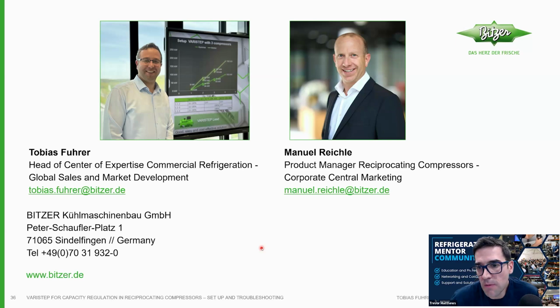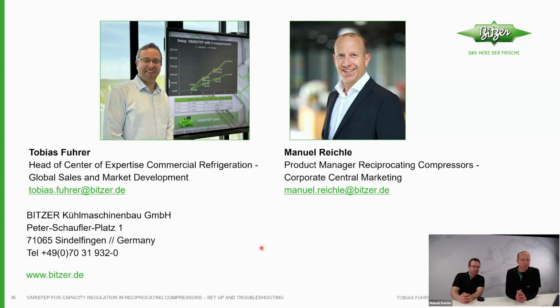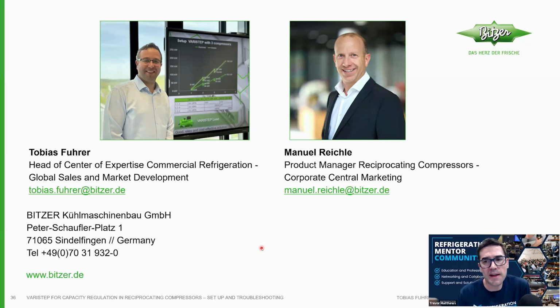Amazing. A couple more here. Thank you so much for your time. The question is, what is the cycle time for the pulse, or is there a cycle time on loading and unloading? It's not a fixed cycle time in the IQ module, but on average, the cycle time is around 30 seconds. Because it's dynamic. It's not really coming from, say, the Danfoss controller or the E3 controller, whatever. It's coming from the IQ module that's actually cycling it.